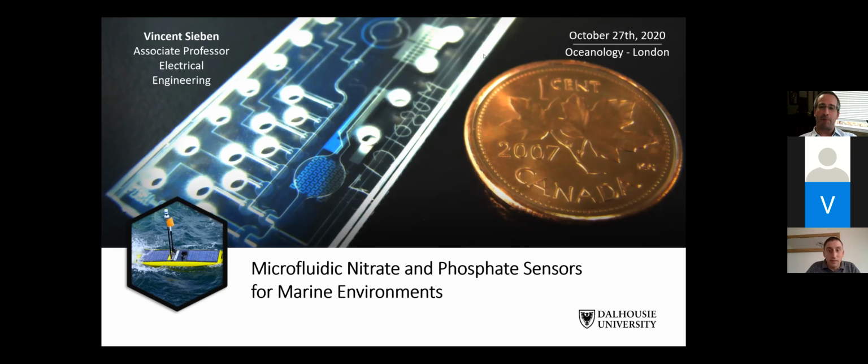So these particular devices that are centimeters in dimension are really capable and efficient devices for handling wet chemistry. So this particular chip automated some 300 steps to perform genetic analysis. And as part of that, there's a lot of functionality that has been miniaturized, including about 20 valves that you see on the chip, miniature valves, thin film heaters, electromagnetic coils for performing particle separations. And so the field has spent the better part of 3 decades making very sophisticated pieces of technology that allow us to miniaturize and perform automated wet chemistry.